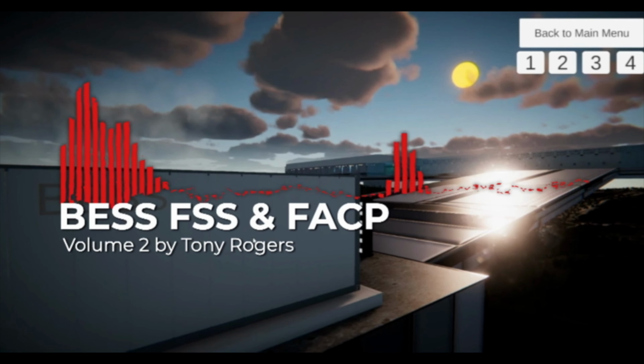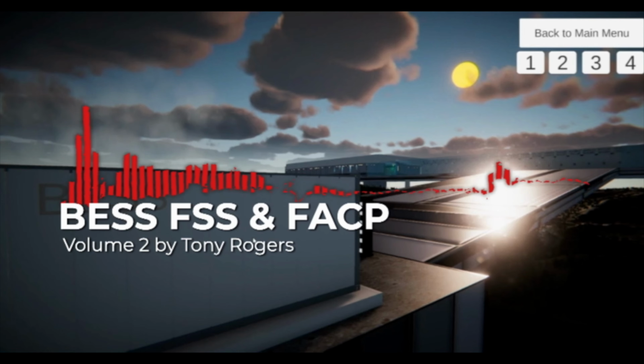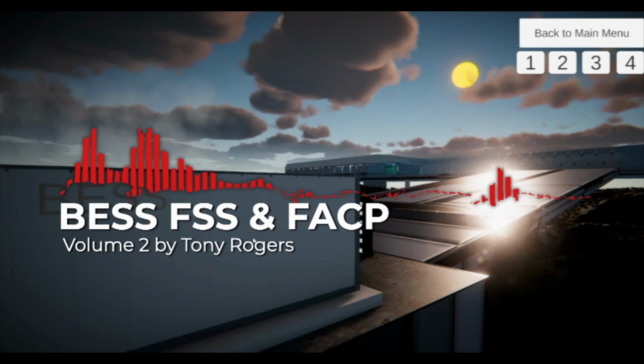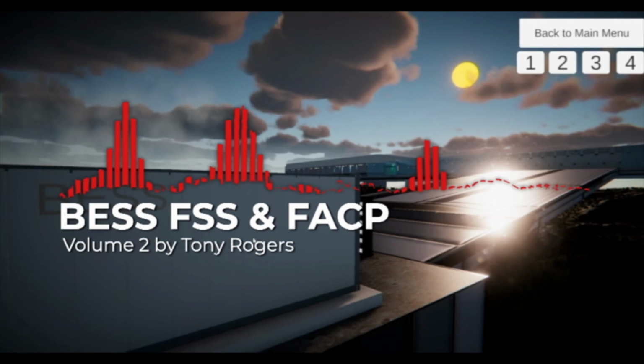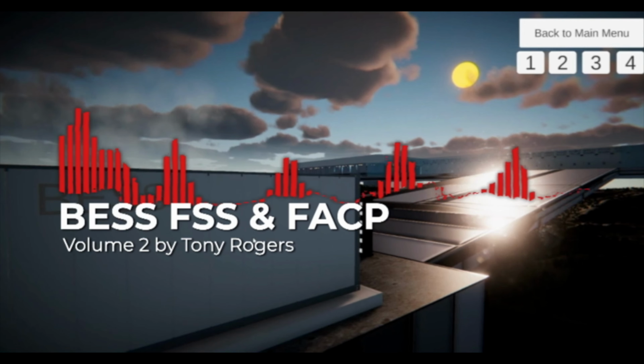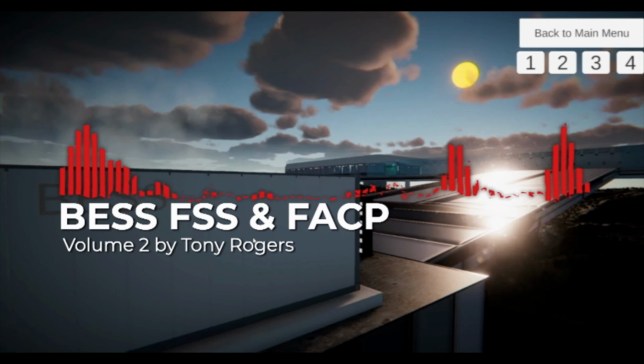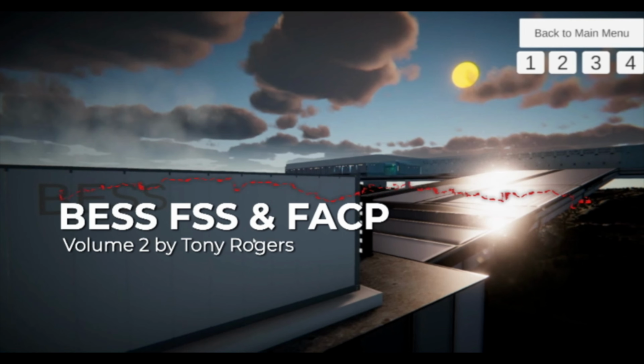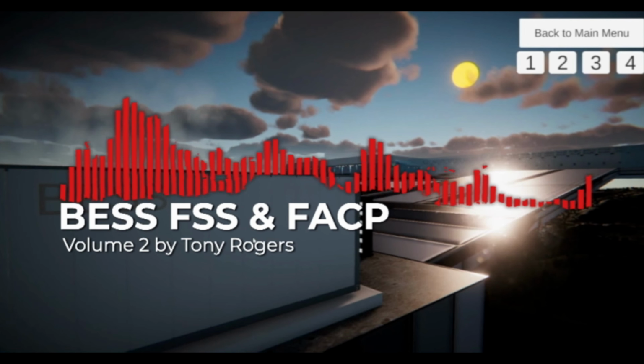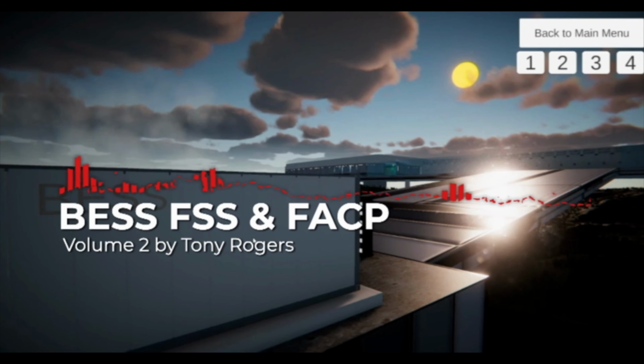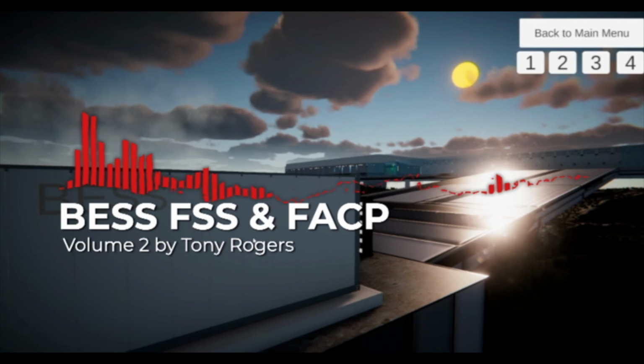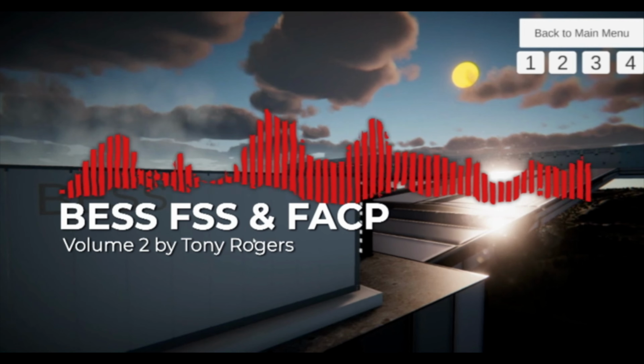Negative aspects of design considerations. While considering design aspects, it is important to be aware of potential limitations and drawbacks. Let's delve into the specific negative aspects of magnetic switches and pressure sensing circuits. Magnetic switches. Although magnetic switches are widely used in fire suppression systems for their simplicity and reliability, they are not without their challenges. One potential concern is their vulnerability to external magnetic fields, which can interfere with their operation and lead to false readings. These external magnetic fields may emanate from nearby equipment, electrical systems, or even natural sources.